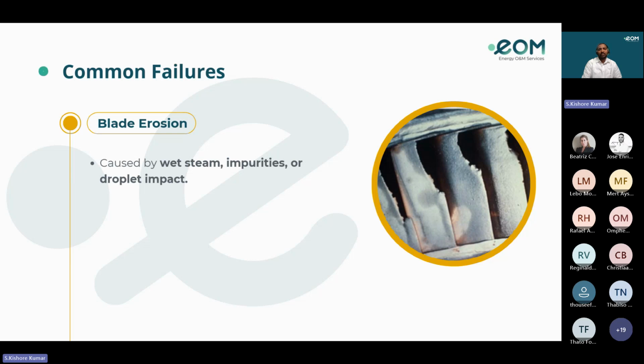Wet steam erosion occurs in low pressure stages where steam becomes saturated or wet. Water droplets in the wet steam impact the blades at high velocities, causing pitting, scalloping, or grooving, especially near the trailing edge of the turbine blades. We can check the blades for erosion whenever the turbine has been stopped, or when we have taken minor outages, by inserting a borescope. It is an instrument with an eyepiece and a camera with light on an insertion tube. We can insert it into the turbine through dedicated inspection ports or access holes to examine internal components like compressor blades or turbine blades, stators and guide vanes.